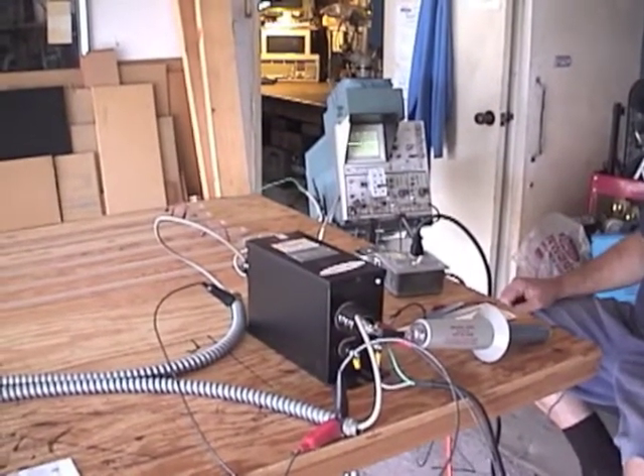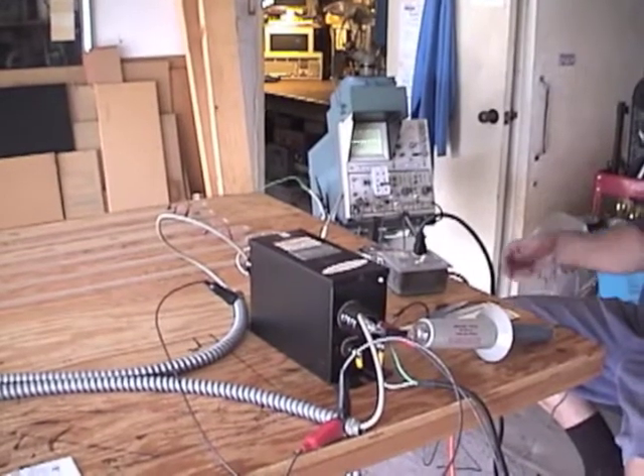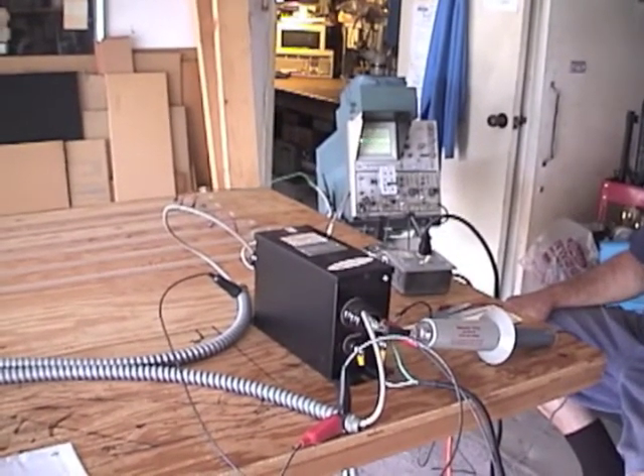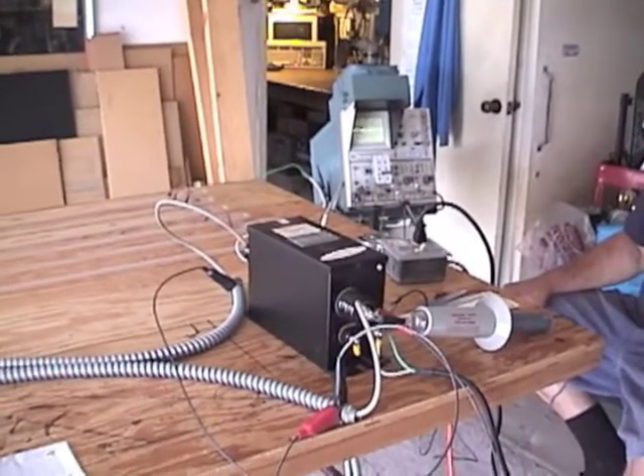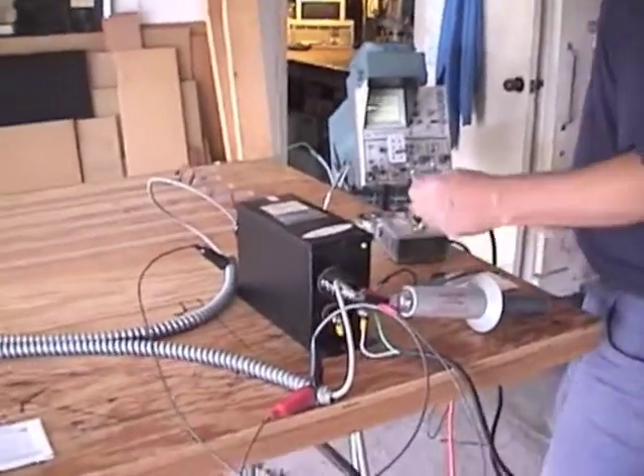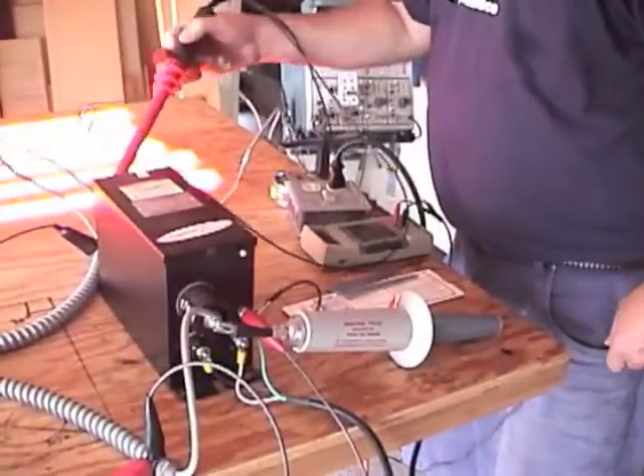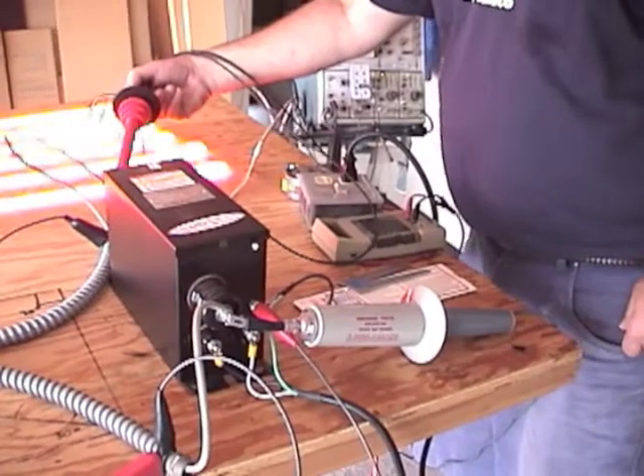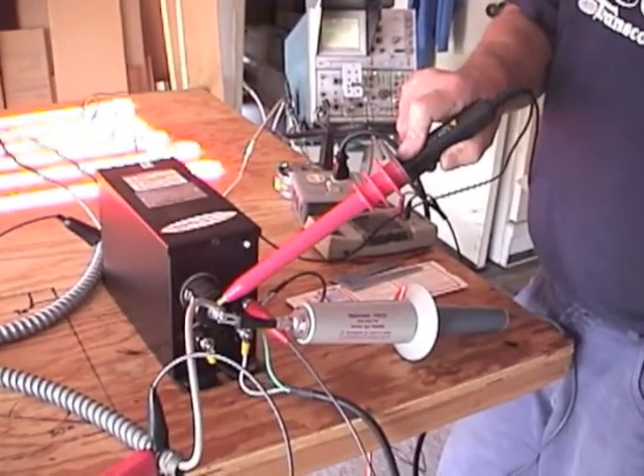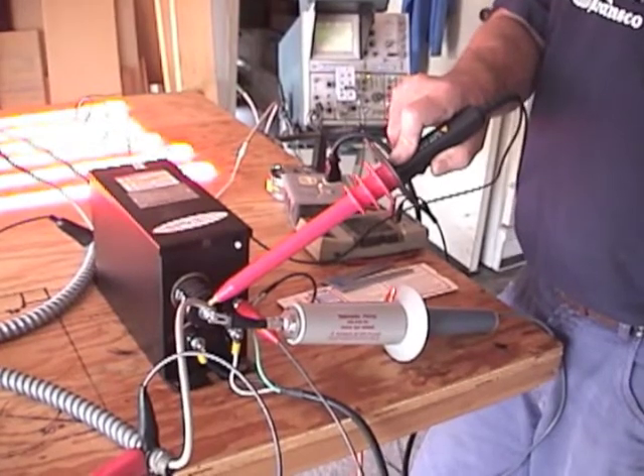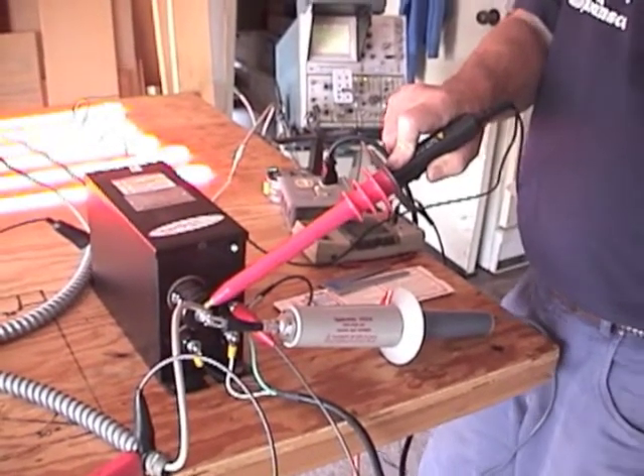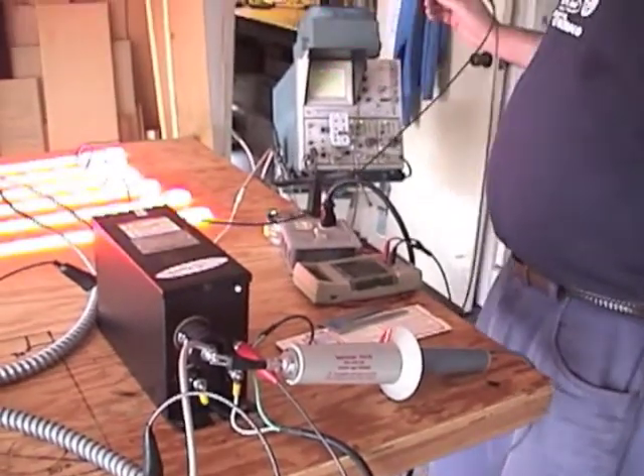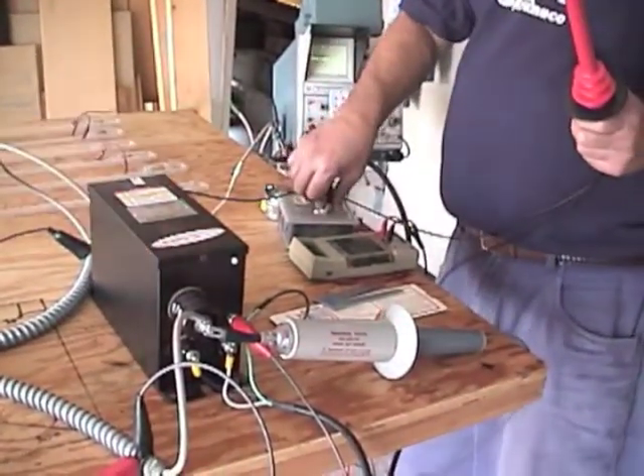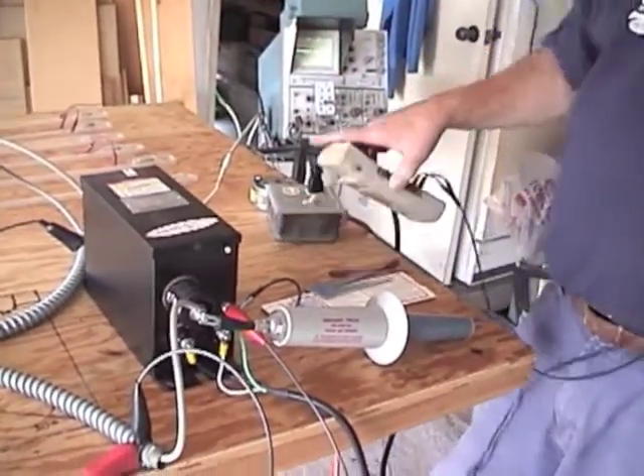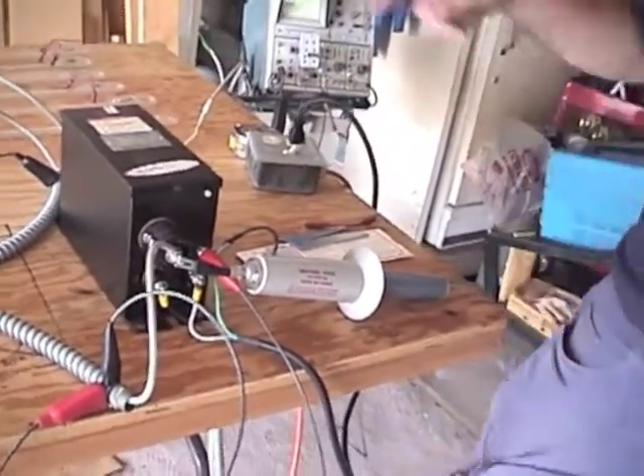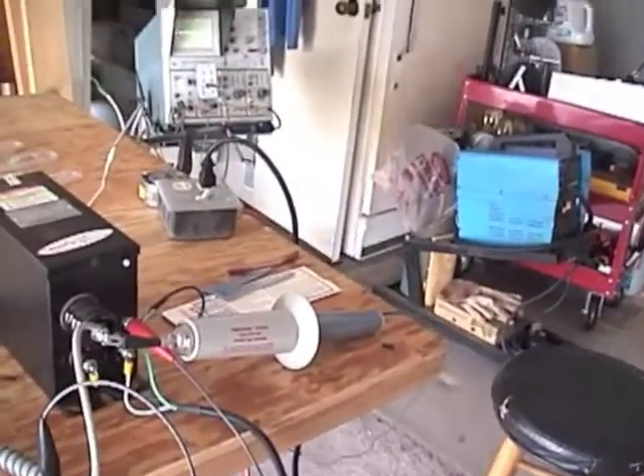Without that, I was measuring, well, what would we expect? We've got 7,500 volts, so we expect to see 3,750 a side, right? Yeah. Okay. And let's just see what the voltmeter says. So this is showing 4 kV a side. But the scope is showing 10 kV spikes.